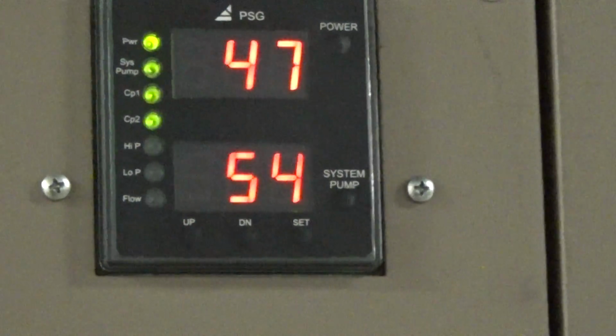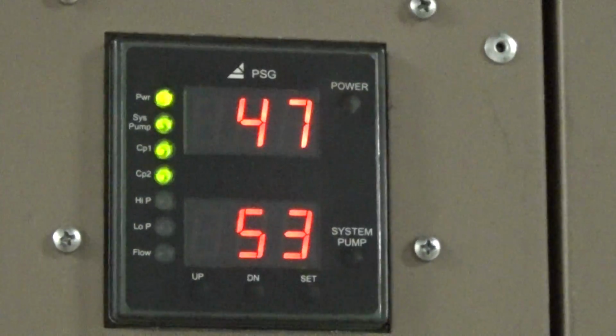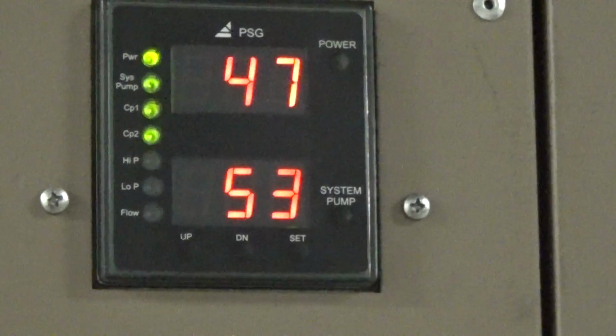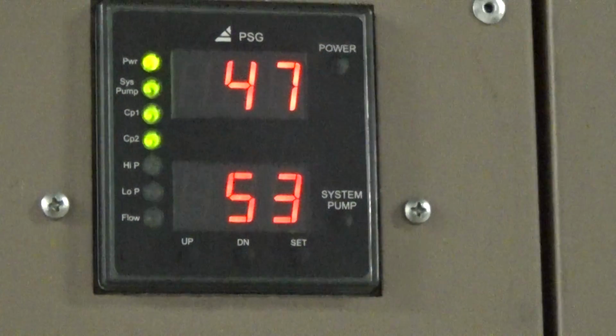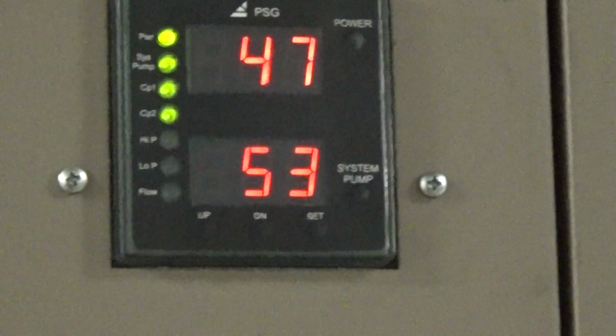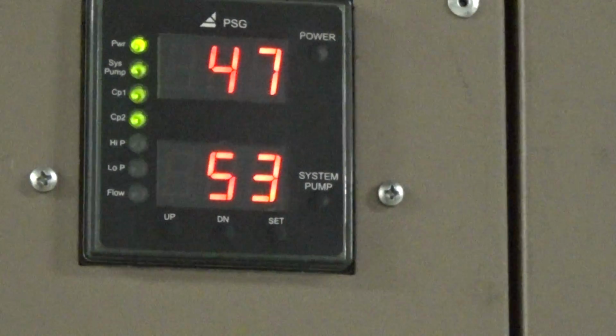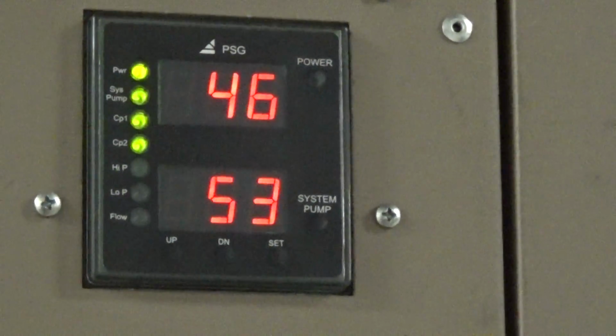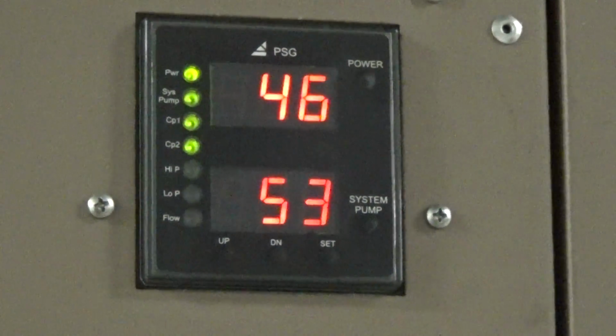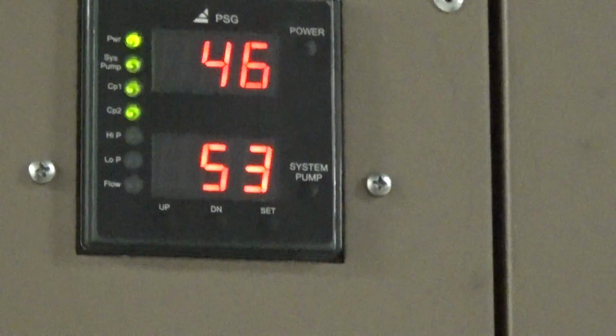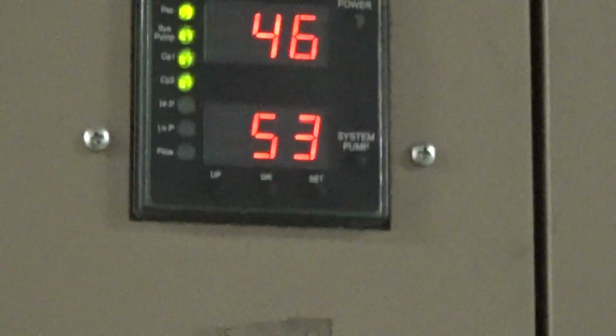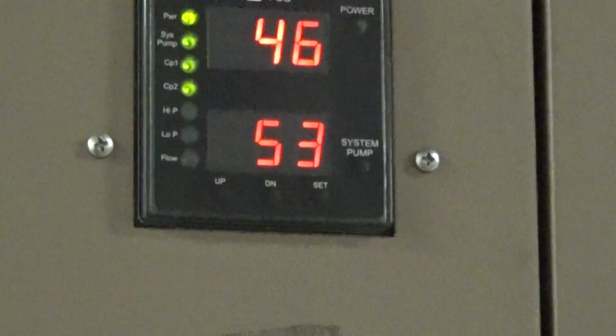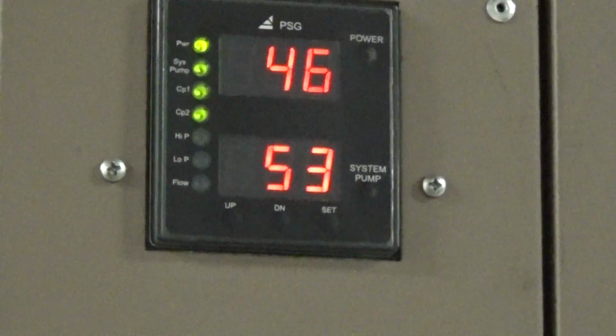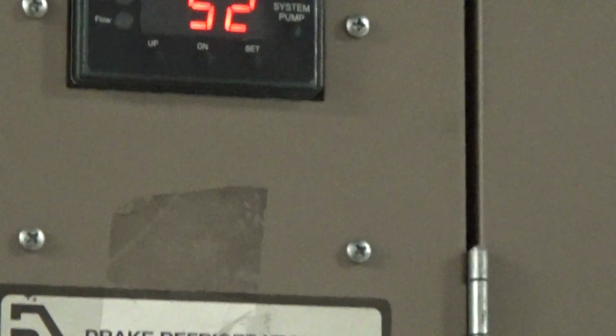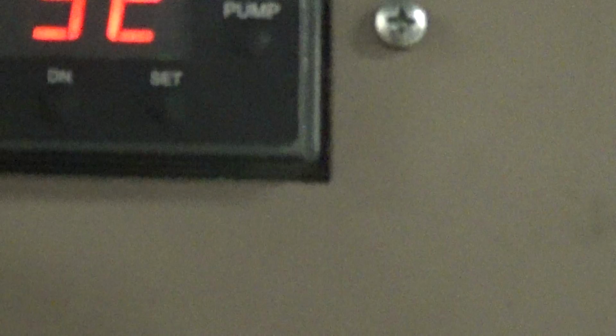So we're obviously sensing temperature off the bottom number here. Those green lights there, the third and fourth one down, are compressor 1 and compressor 2. So compressor 2, which had the 52-degree set point, just turned off. Compressor 1 is still running.